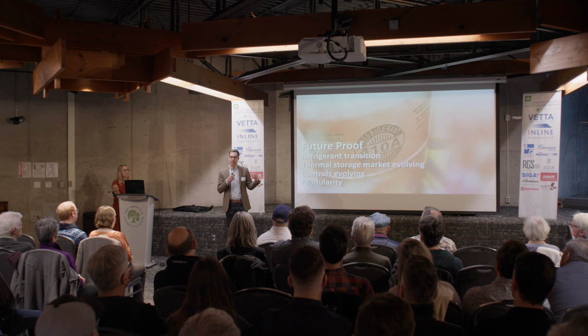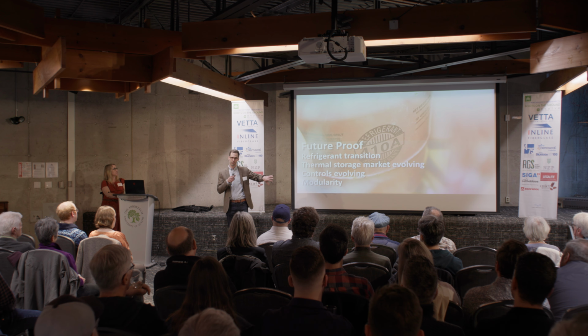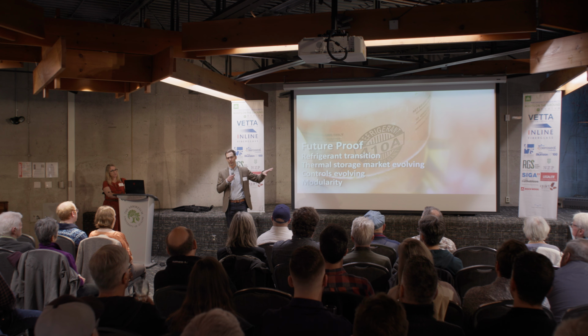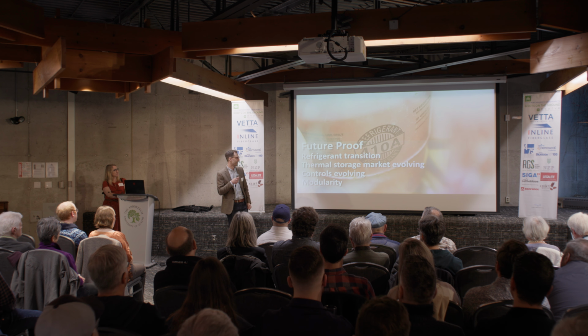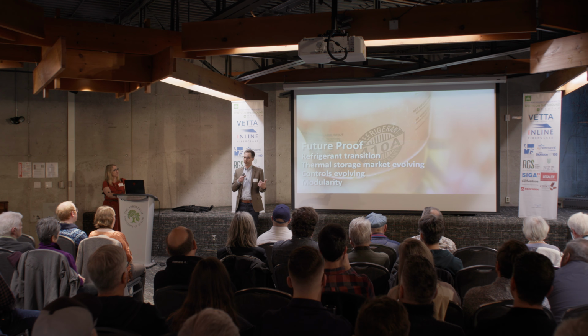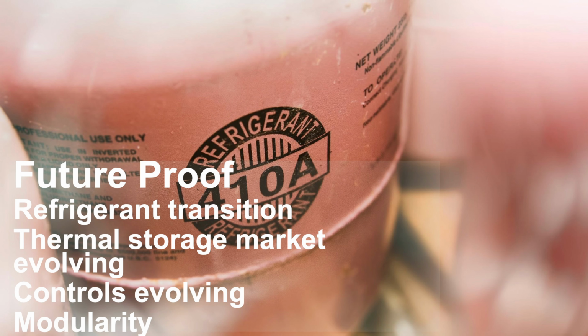Most of the air-to-water heat pumps sold over there are R290. But if we set up the system to have hydronic distribution and all the refrigerants in the yard, then we don't really care. When the heat pump we buy is at end of life, we can swap it out without having to do a major overhaul because we're not bringing any refrigerant lines into the house. The thermal storage market is evolving, so I'm not doing any of that on day one really, but we could add it in the future, which speaks to the modularity of these systems, that they can be repiped and modified as time goes on.